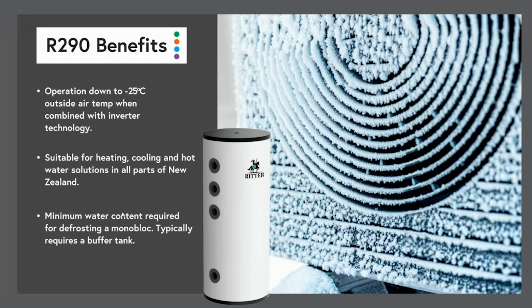So the water will freeze and it will start building up and create ice. If it's left unchecked, it will just get icier and thicker, and the heat pump knows this is happening because the ice acts as an insulator and prevents it from performing well, so it will automatically go into a defrosting mode to try and clear that ice off the coil. Now the question is, where does it get its heat from to do this?